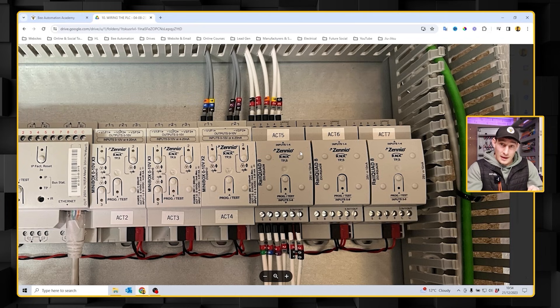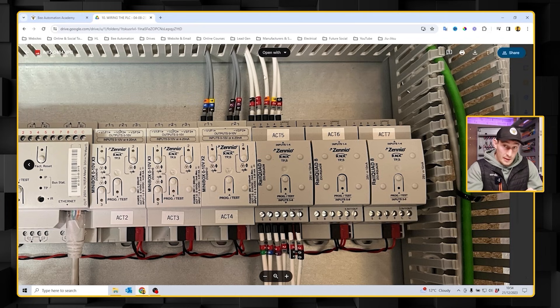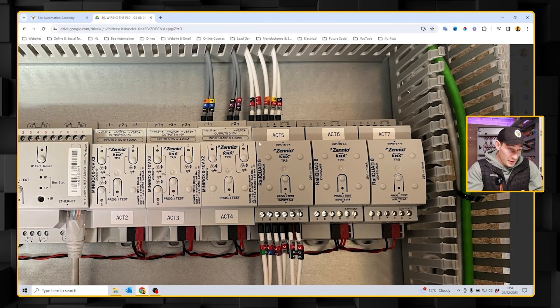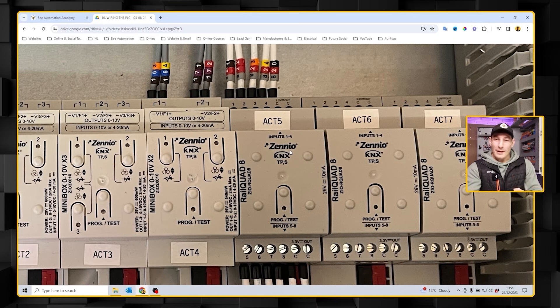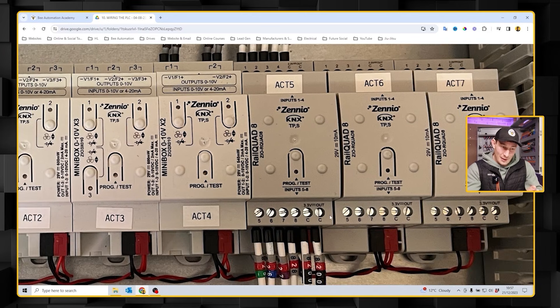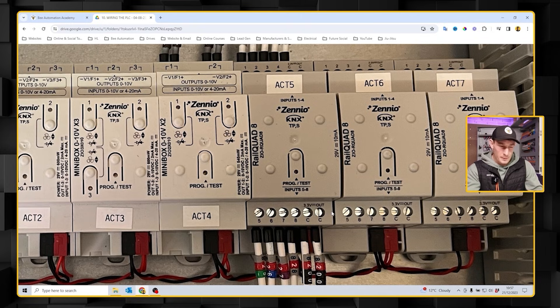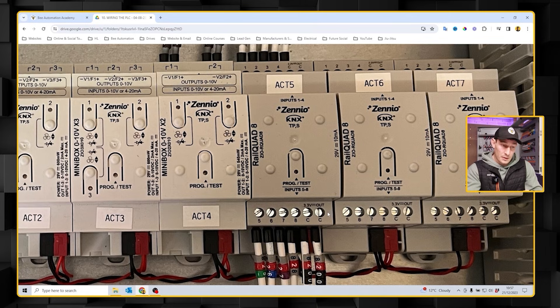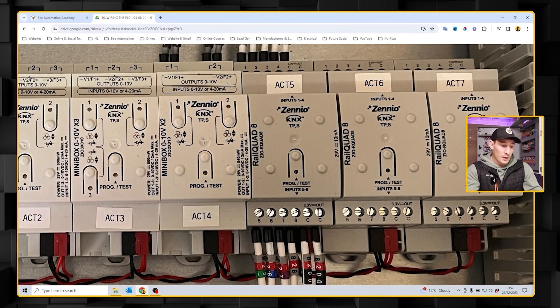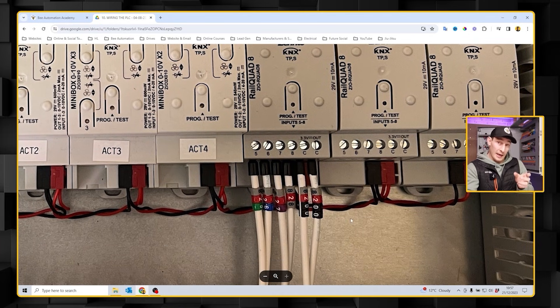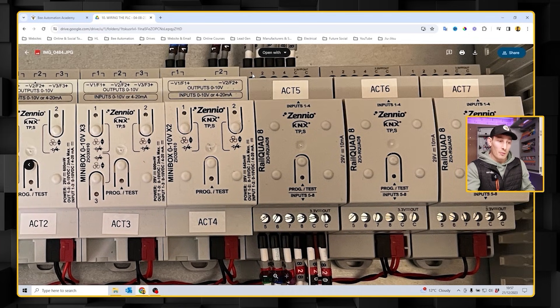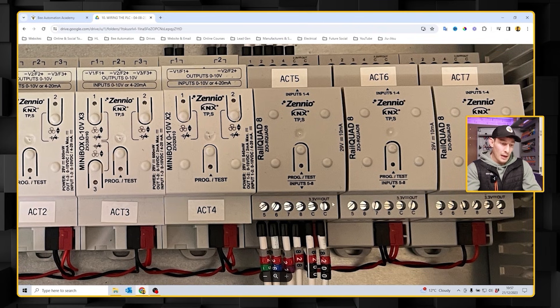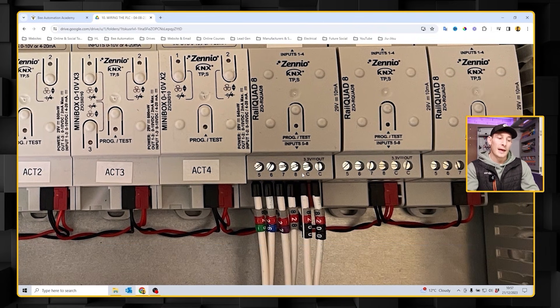Now let's look at the digital input signals. These white cables are feeding into Act 5 and you can see we've got eight inputs, four on the top and four on the bottom. A little bit more detail on these digital inputs - I like to refer to these little circuits on this PLC as closed loop circuits. We've got 3.3 volts going out on the C terminals, the common terminals, and ultimately it's coming back to the input terminals one through eight, and that completes the circuit.